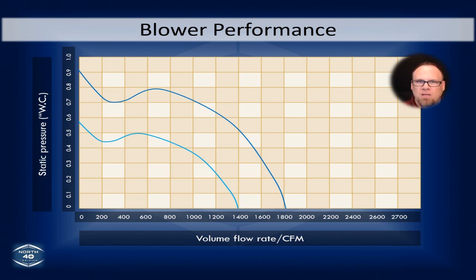Okay, so bear with me. On the left-hand side of this chart that you're looking at, you see numbers going up and down, and that's what's called static pressure. It's measured in inches of water column on a manometer. Now, static pressure is a fancy word for resistance. How much resistance is in that ductwork, and that's what you're measuring with your manometer. So going up and down that chart, as you go all the way up to the top and you see the number 1, that is 1 inch of static. In most applications, that is way more than you would ever want, okay? But in this particular example, that's the maximum amount. You can't get any more than that, okay?